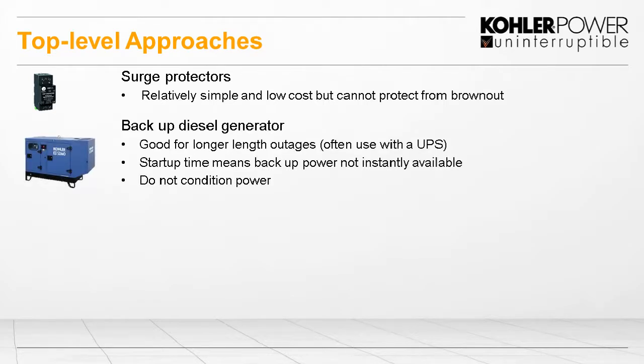Next one would be the backup diesel generators. Now these are very good for long outages, but the startup time means that power isn't instantly available. So these are often used with a UPS. And in normal time, they won't condition the power. It's only when they're online are they giving conditioned power.